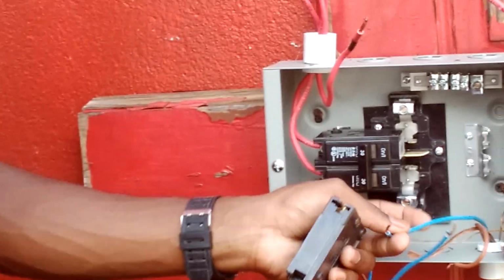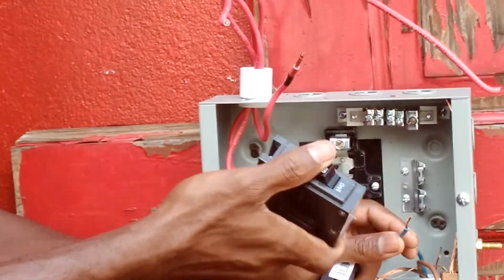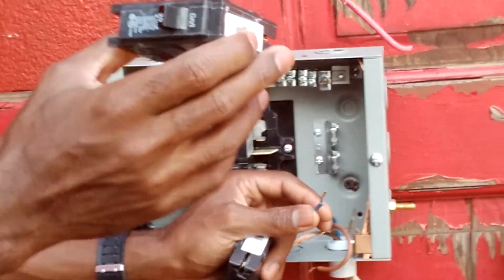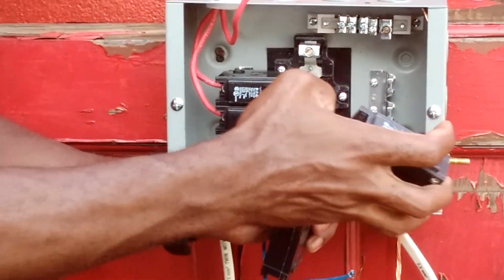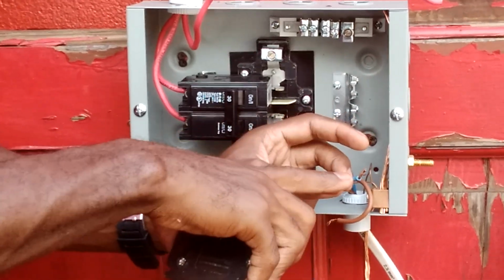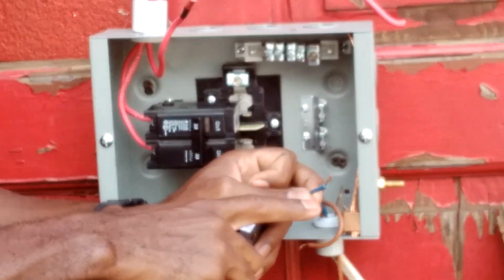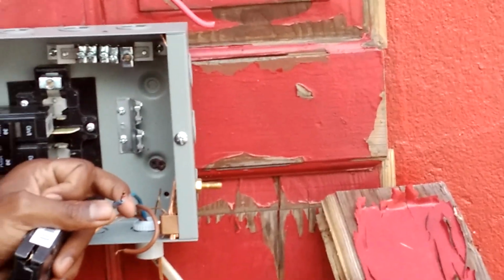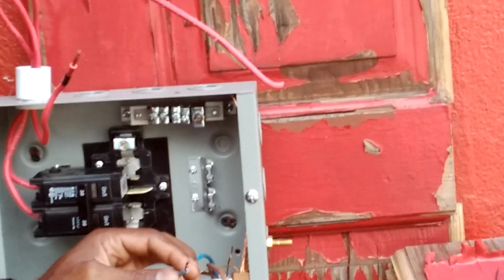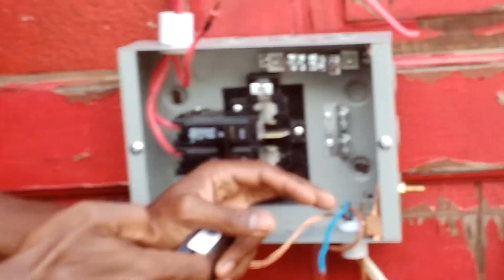This is a 2.5 millimeter wire, and we use the 20 amp to protect it, because anything over 20 amp, this wire also begins to burn. So the 2.5 would be American wire gauge number 12 - that's what this 2.5 wire would have been.